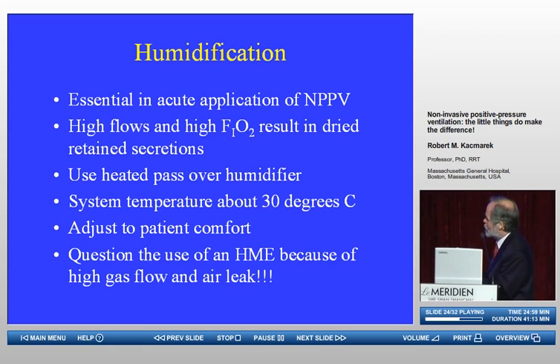Now, it's difficult to know how to set these. As you see, I've got about 30 degrees centigrade. We set it to patient comfort. You can use a heated single-limb circuit in your non-invasive gas delivery system. If you're using an ICU ventilator, it's even easier, because you can use the typical heated circuits to avoid this problem, or an active humidifier without a heated circuit, although you have an issue with accumulation of secretions.